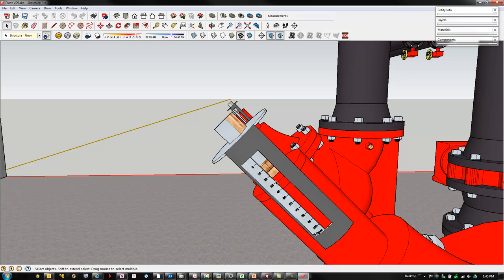In fact, the fundamental equation for pump brake horsepower is flow times static divided by a unit's conversion constant, the pump efficiency. So anything we do to lower the head, the static pressure, I said static, I thought of the fan, flow times pump head divided by the unit's conversion constant and the pump's efficiency gives you the brake horsepower. So anything you do to reduce the head on the pump potentially will save energy, especially if you can reduce the head with the flow at the design number.